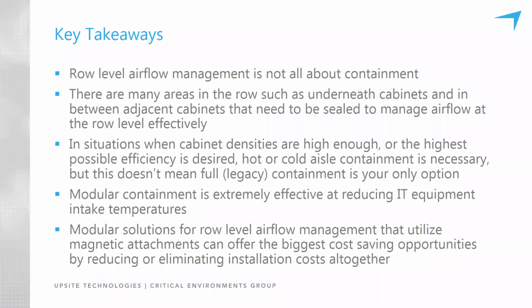So here are some of the key takeaways from the presentation. Again, with regard to row level airflow management, it's not all about containment, right? There are a lot of areas in your data centers, in your rows, where you can start making these initial low level investments. These are all lower cost, higher value investments. It's real important, just like at the rack level with the blanking panels and sealing off gaps between the side panels and the rails and all of those things. The same thing applies with the row levels.